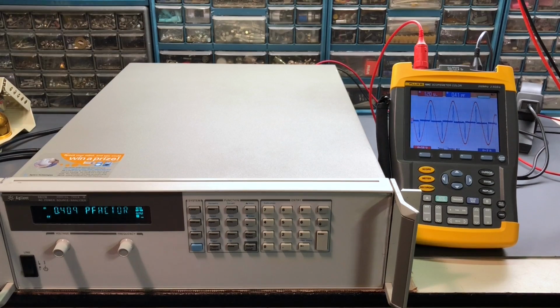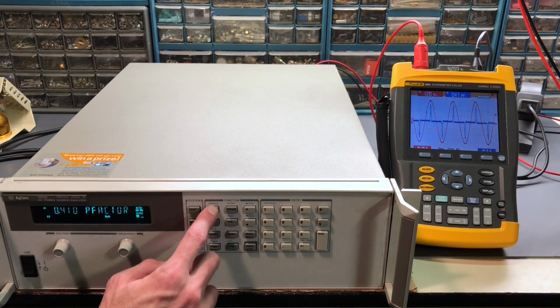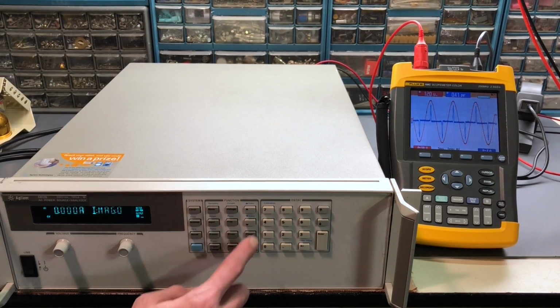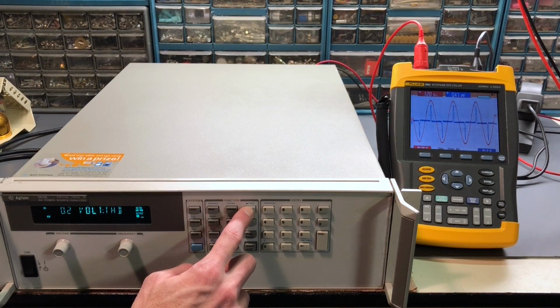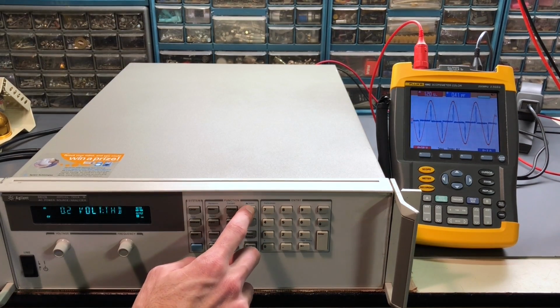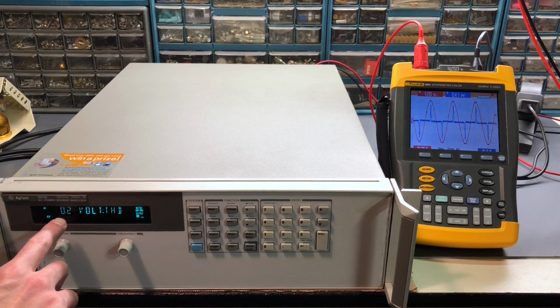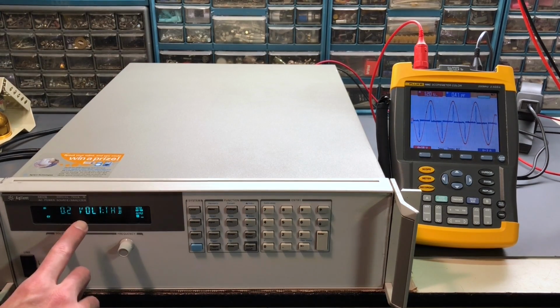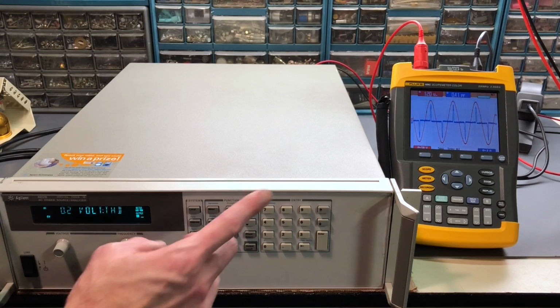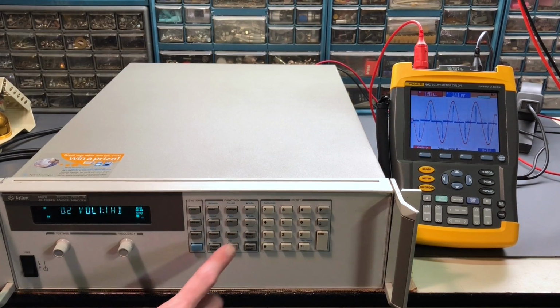Now we can come over here and look at the distortion. If we go to shift here, harmonic, we can see it says 0.2% total harmonic distortion on the voltage waveform, and we do have a nice sinusoidal waveform over there, so that makes sense. Look at that current waveform. The total harmonic distortion is 91.2, so a lot of distortion on the current waveform.